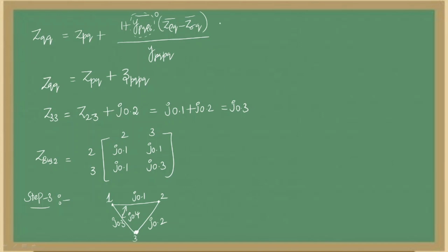Now, let me know how can I find Z bus matrix for this addition. If you observe, 1 is a reference node and it is already an existing node. 3 is also an existing node. As we are adding an element between two existing nodes, we need to consider this as a link. So we need to use the mathematical expressions related to addition of a link, right?